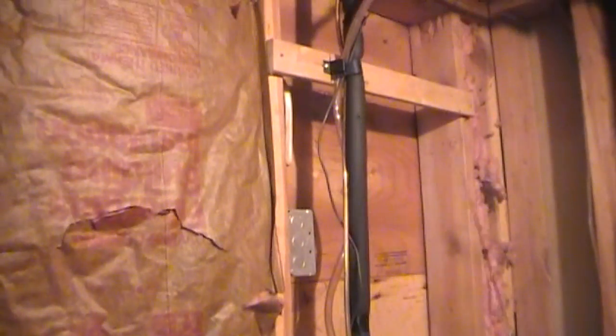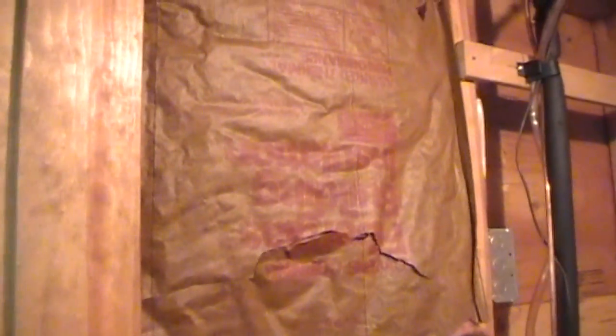Behind these layers is about an inch of exterior plywood and some building paper. On the inside of most of the house there's gypsum board, and on the outside there's vinyl siding. Taking all of this into account, I calculated that for every 2-foot section of this exterior wall, around 10.3 BTUs per hour are lost.